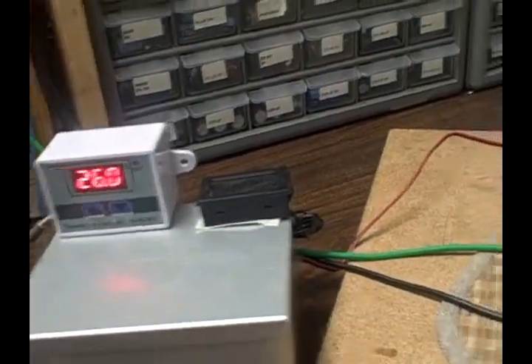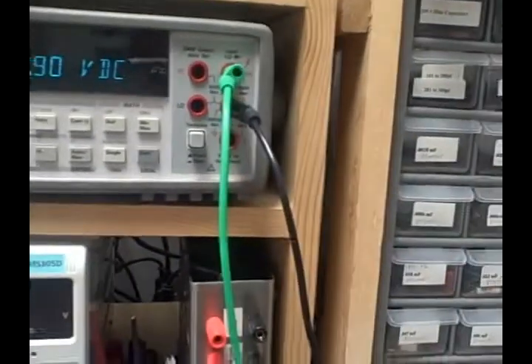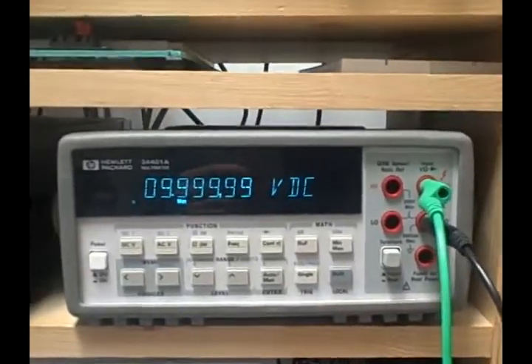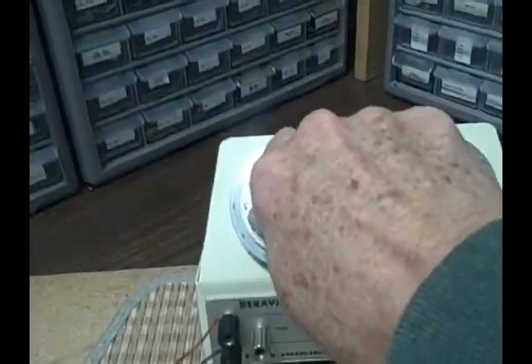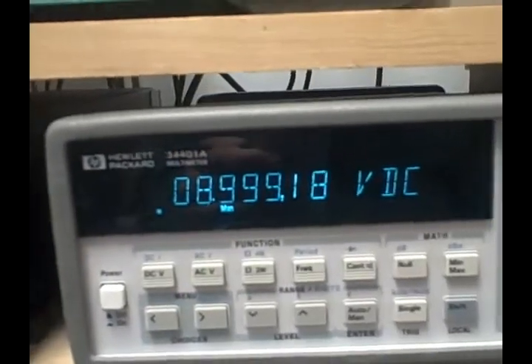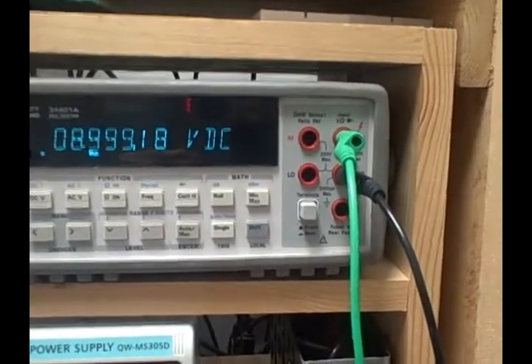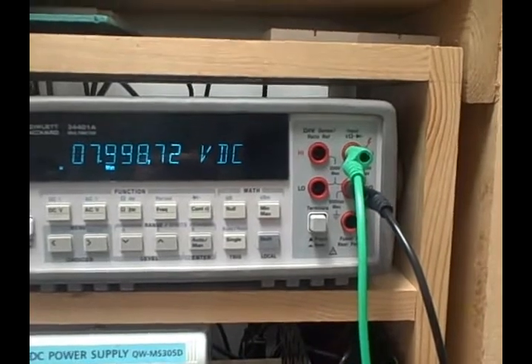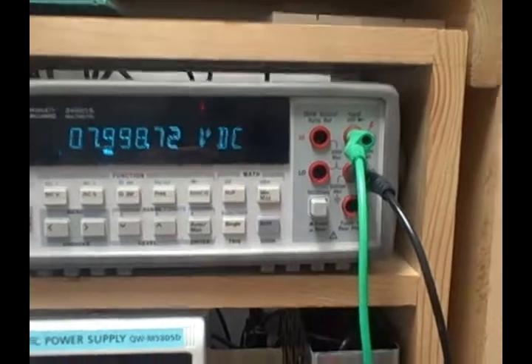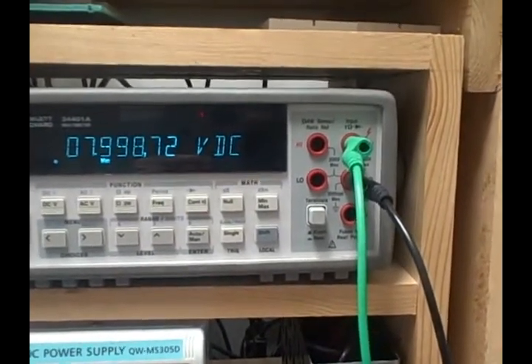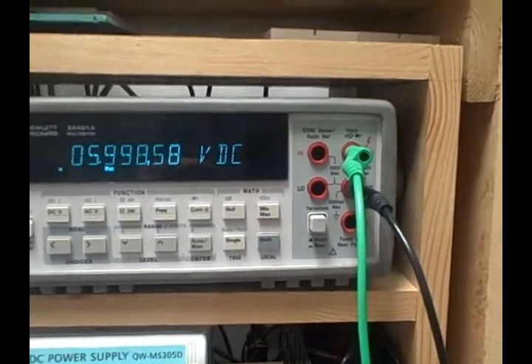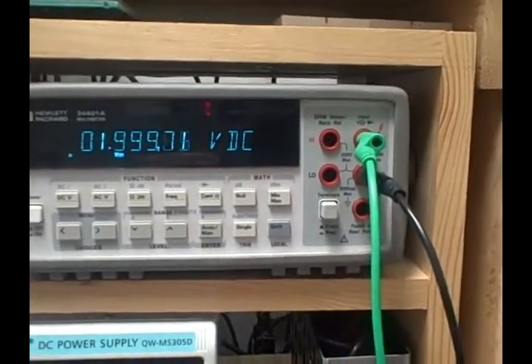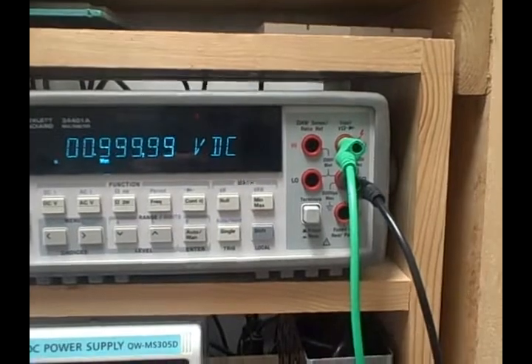We're holding it and we're able to divide. I mean if I can take myself for instance, let's go back up to all nines. I'll take the major division step, go down one. We went from nine to an eight and we see that we are at 8.999. Now in the larger voltages on this major step I'm going to see that I won't be perfect. There is some error 7.99872. I'd like to have all nines there after the seven. 6.99849, 5.99858 and then as I go down to zero I begin to get more accuracy.